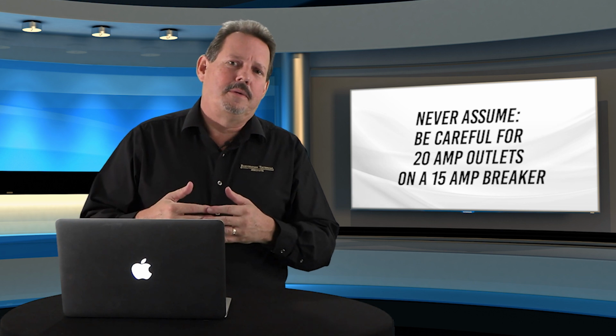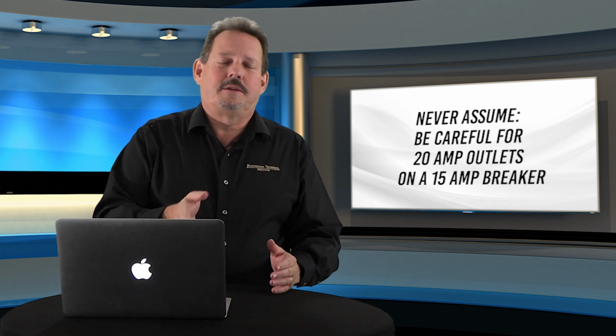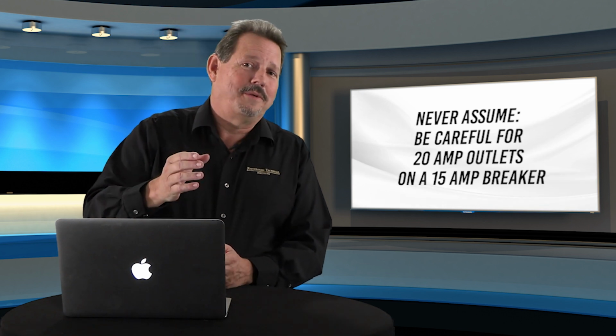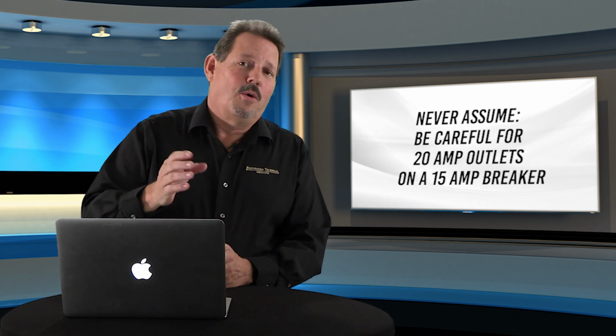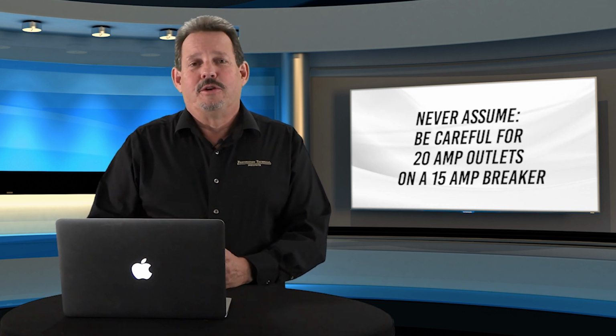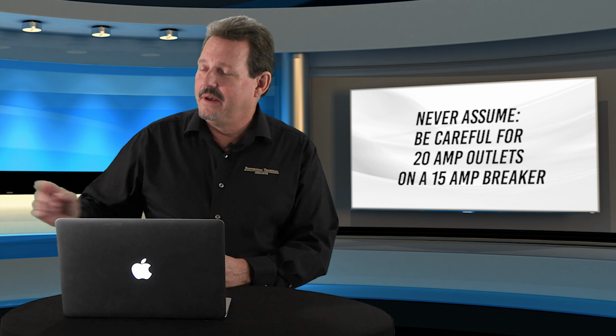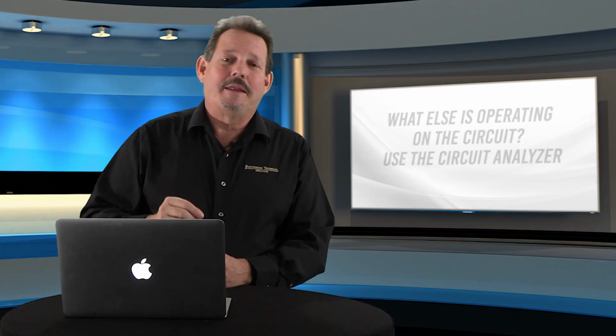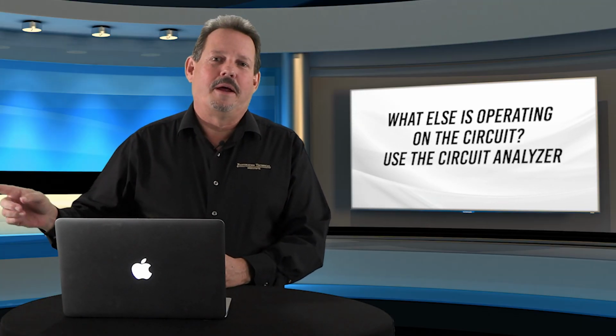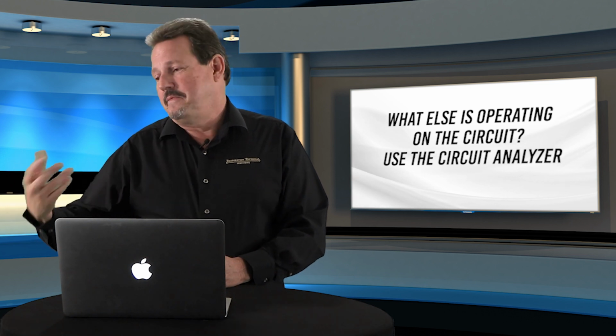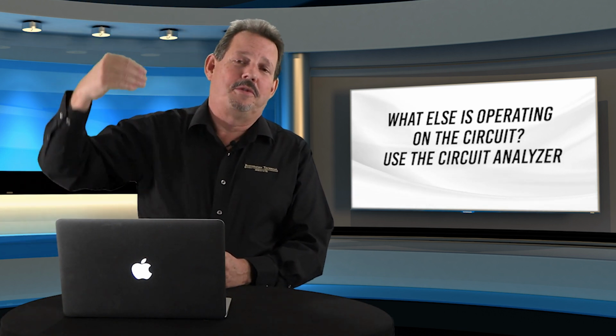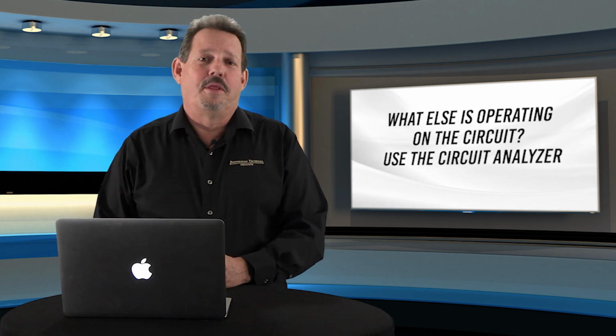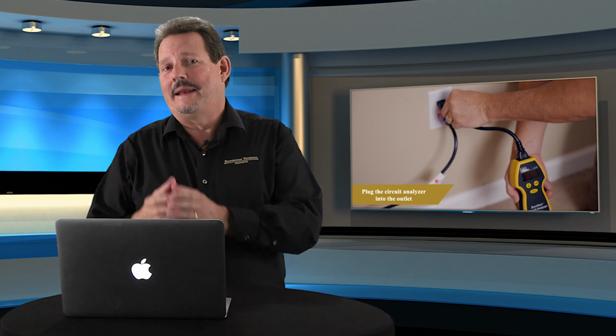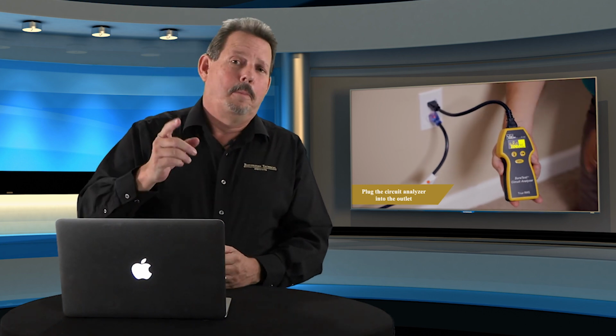Secondly, there's always the possibility of the customer replacing the outlet with a 20 amp outlet, or a grounded outlet where there is no ground supply, or even only a 15 amp breaker behind it. So never assume that because the outlet is a 20 amp outlet, the circuit breaker is also a 20 amp circuit breaker. And never assume there's nothing else running on that outlet. It could be going to multiple floors or multiple rooms, with other items using electricity, so you might not even have that full 12 or full 16. The best way to check this is with the circuit analyzer shown here.